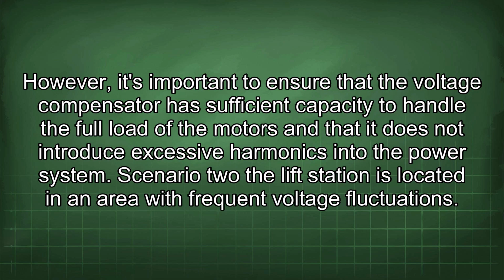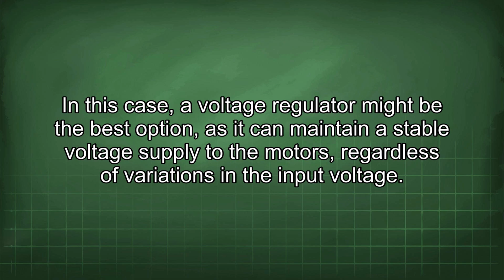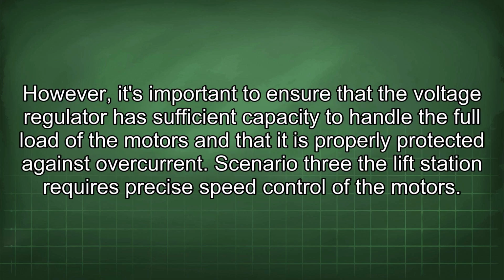Scenario 2: the lift station is located in an area with frequent voltage fluctuations. In this case, a voltage regulator might be the best option, as it can maintain a stable voltage supply to the motors regardless of variations in the input voltage. However, it's important to ensure that the voltage regulator has sufficient capacity to handle the full load of the motors and that it is properly protected against overcurrent.